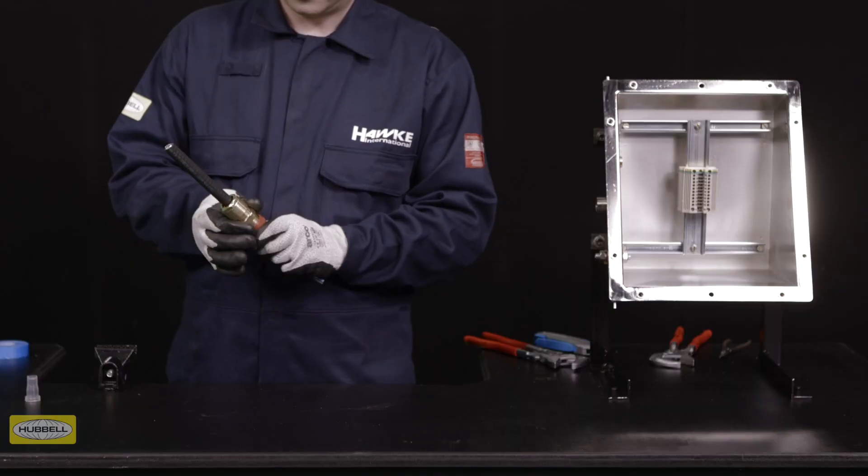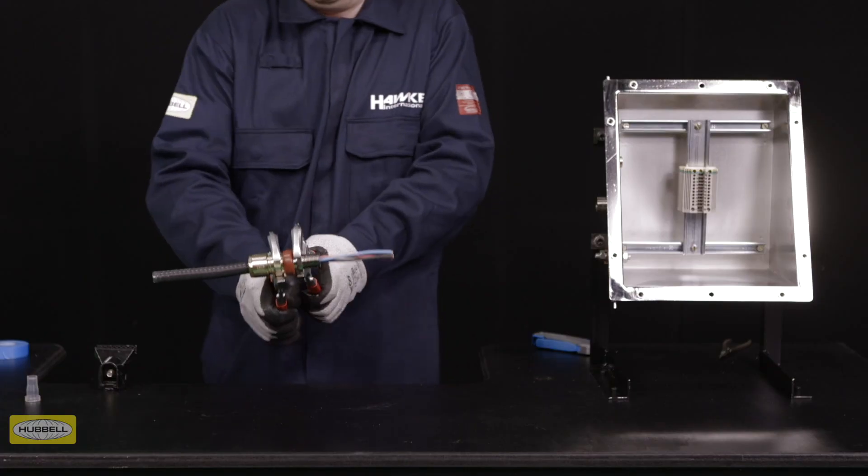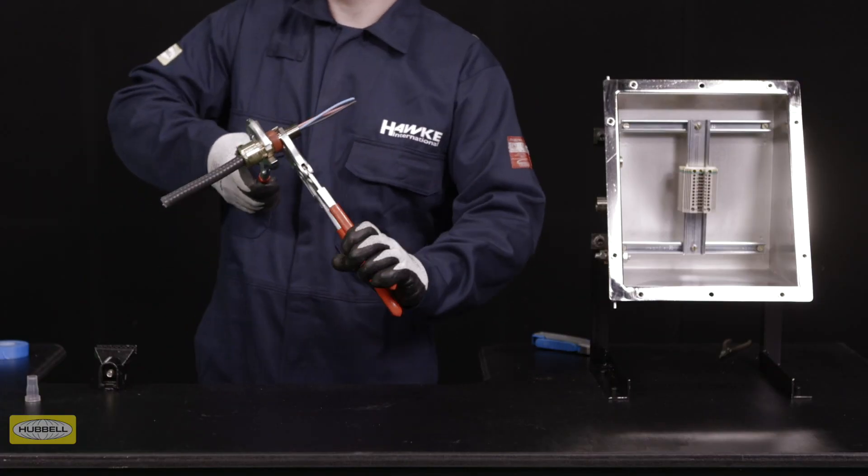Ensuring that the Diablo stays in place, tighten the middle nut onto the entry with a wrench until the Diablo grips the metal clad sheath. Tighten the middle nut a further half turn with a wrench.